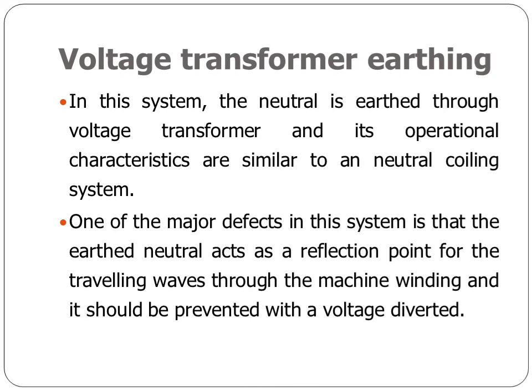Voltage transformer earthing. In this system, the neutral is earthed through the voltage transformer and its operational characteristics are similar to the neutral coil system. One of the major defects of the system is that the earthed neutral acts as a reflection point for the traveling waves through the machine winding, and it should be prevented.